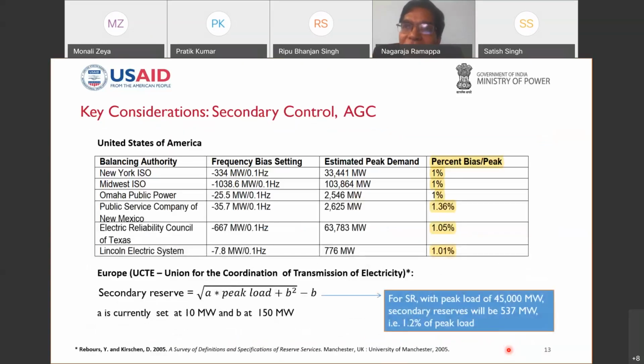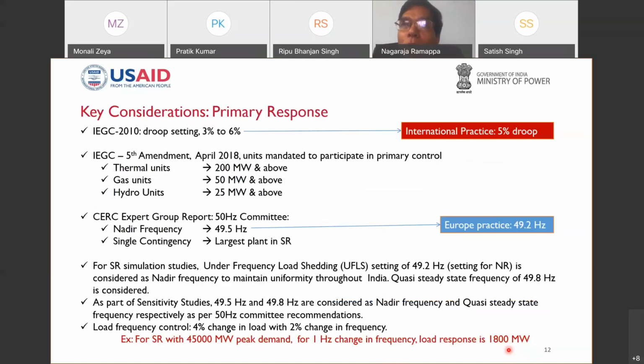Now, just to give a context, if you take the entire Indian grid, this power number is to the tune of almost 6,000 to 7,000 megawatt. Maybe some expert from the POSOCO will be able to comment, but it is very important to understand that interconnection of the entire Indian grid has helped us to improve the power number. Even if a 4,000 megawatt UMPP plant is lost, our frequency from 50 Hertz will not come down below 49 Hertz, because the entire system frequency gets adjusted just because of the load response. Next, please.